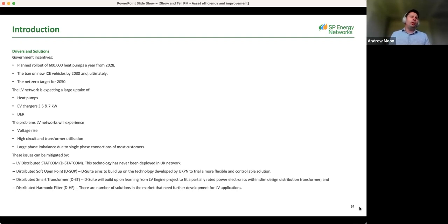On interconnected networks, we can see load sharing unevenly between secondary substations, which can lead to low impedance paths getting more of the load, with those transformers nearing their limits while other transformers are underutilized. As we put heat pumps and large, continually operating loads onto the network, we could see large phase imbalances, increasing the utilization of one phase while leaving other LV phases fairly unutilized.